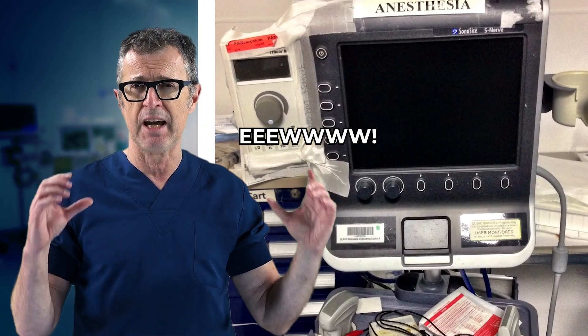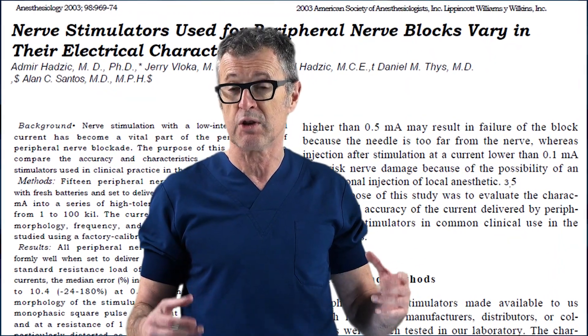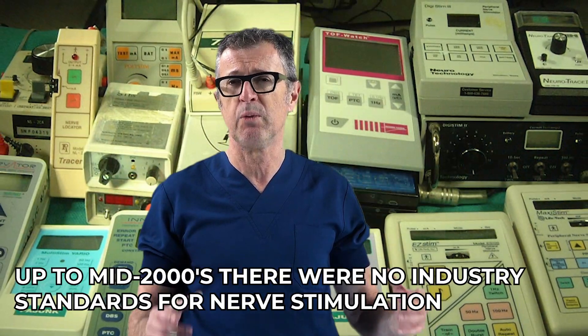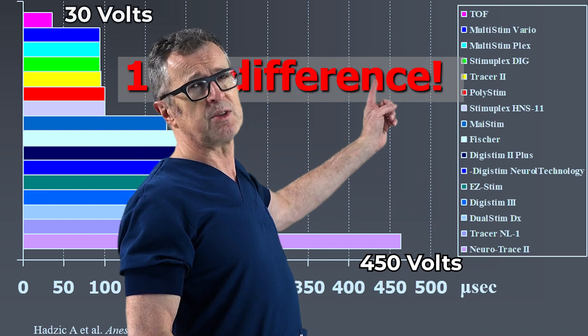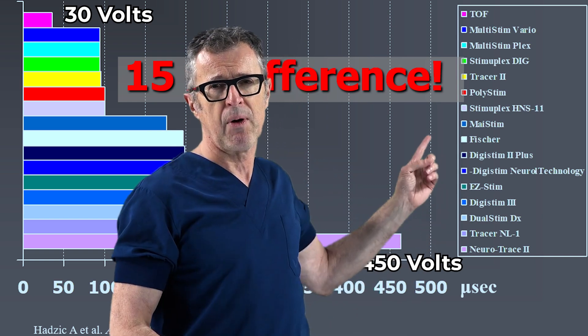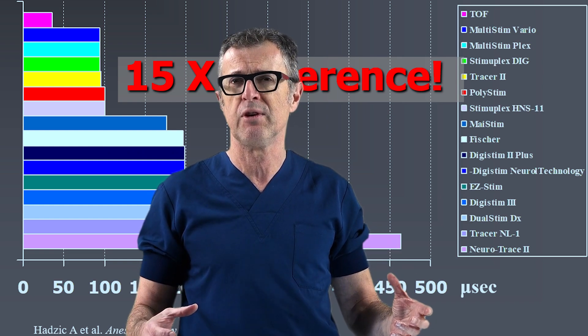However, they do provide information that can be extremely useful and protective of the nerves. When we published a study in Anesthesiology in 2003 about the electrical characteristics of commercially available nerve stimulators for nerve blocks, it was simply unbelievable that there was no standard whatsoever regarding their electrical characteristics. Some units put out as much as 450 volts, whereas others were limited to 30 volts or less. Based on these results, our paper completely changed the industry and set out the standard electrical characteristics for the manufacturing standards of peripheral nerve stimulators.